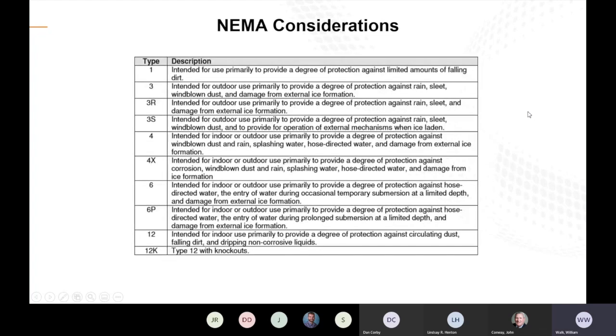So when it comes to those extreme situations that we talked about, you have a couple of NEMA considerations. For example, you have type 1, which is going to protect from falling dirt, stuff like that. For example, NEMA 12, where it's going to protect your drive from dust, falling dirt, non-corrosive liquids, all the way up to 4X, which will provide protection from corrosion, dust, rain.